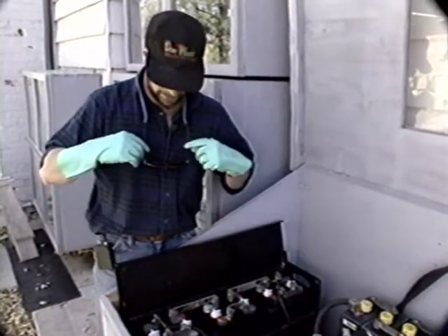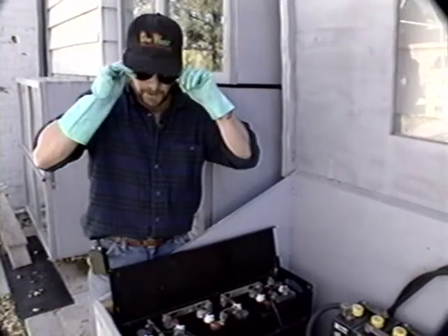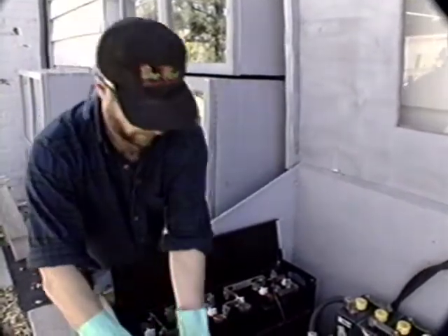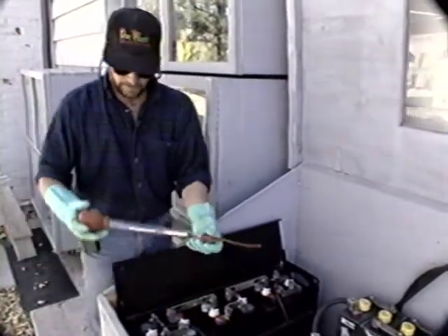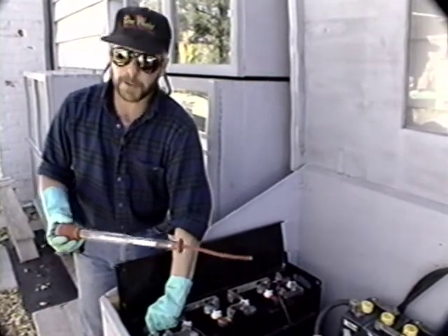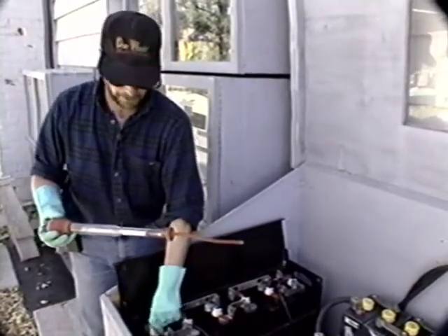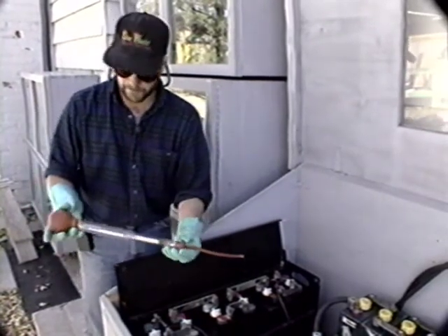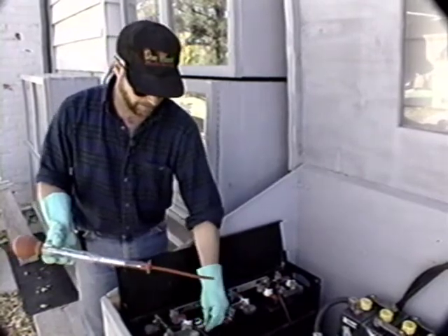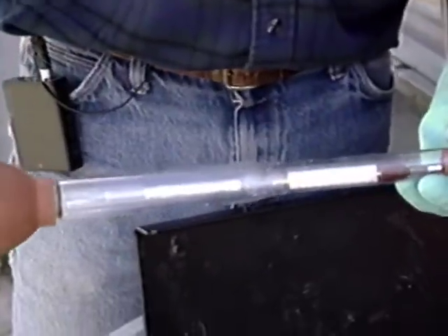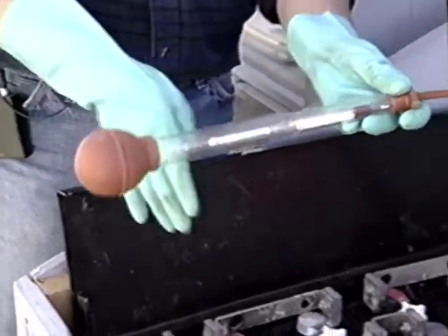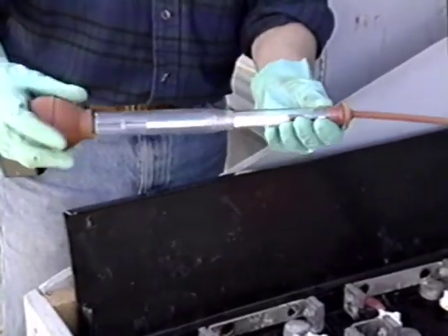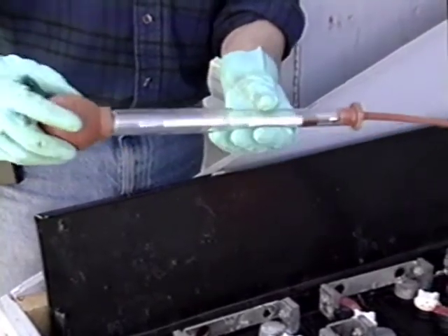Whenever you're doing battery maintenance, it's very important to have some safety equipment. Eye protection is critical. Rubber gloves are real important. This instrument here is what we use to measure the specific gravity, the real state of charge of a battery. It's called a hydrometer. And we recommend that PV system owners use a hydrometer at least twice a year to test every cell in their battery bank, every battery in their battery bank, and make sure that they have a good equalization in the specific gravity of all those different battery cells. Let's go ahead and do a brief hydrometer test right now.